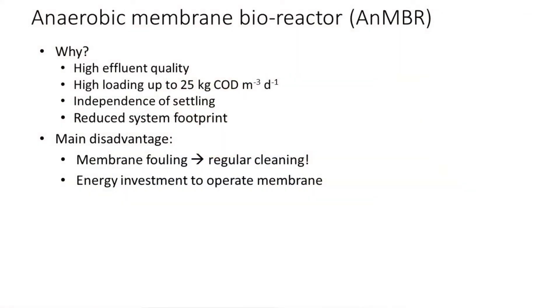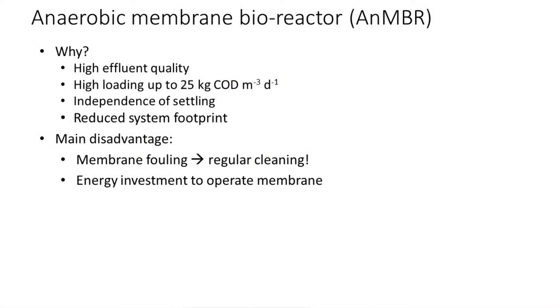The anaerobic membrane bioreactor is basically a digester with a membrane keeping the solids inside and just pulling out the effluent. The advantage: pulling water through a fine membrane guarantees good effluent quality — bacteria and pathogens are stopped by the membrane. You can load it very highly since you're not depending on settling, and you can work very compact. Disadvantages: pushing wastewater through a membrane costs energy, membranes are an investment, and they will foul over time, requiring regular cleaning.